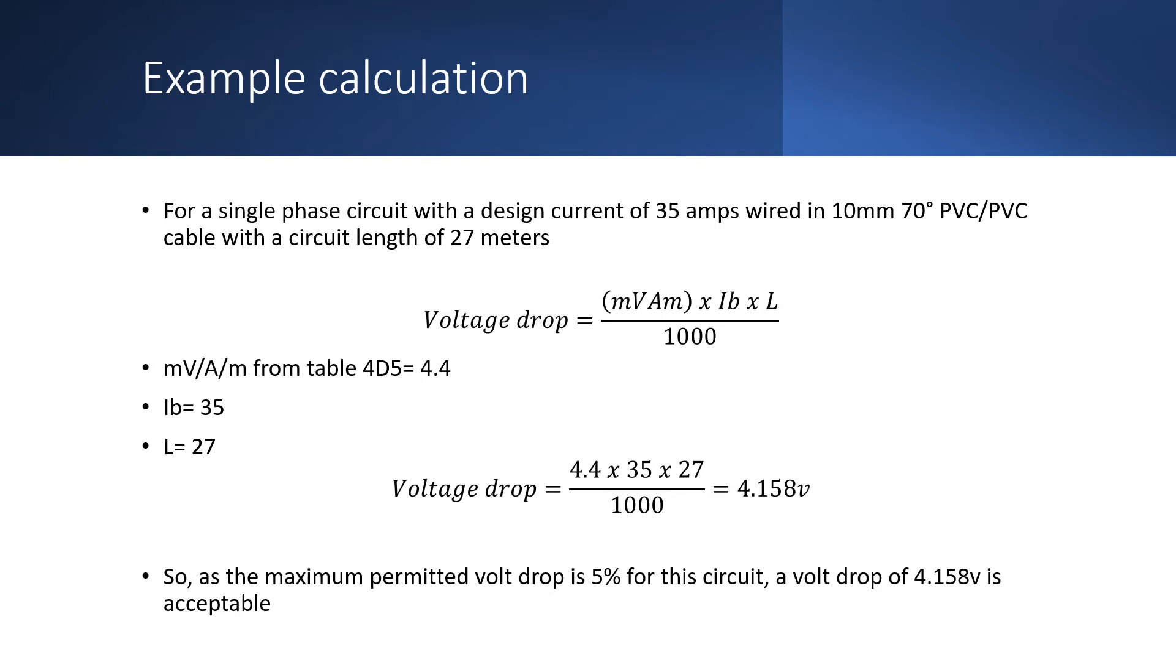The design current is 35. The length of the circuit is 27. So the equation becomes voltage drop equals 4.4 multiplied by 35 multiplied by 27 and then divided by 1000, and that gives us an answer of 4.158 volts. So as the maximum permitted volt drop is 5% for this circuit, a volt drop of 4.158 volts is acceptable.